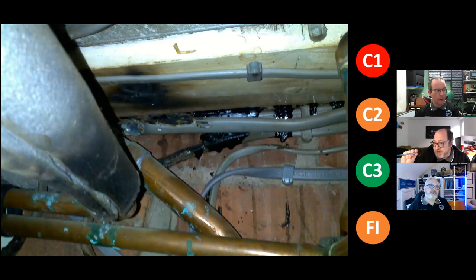I immediately want to get closer to that cable to see if there is exposed conductor, and I want to test that, because obviously, inspection and testing. It might be that I haven't tested this yet, and under an IR test I can actually confirm that there is damage to this cable. But again, that cable might not be damaged so much that the testing would find that problem. So this kind of inspection increases the need for us to take inspection seriously.